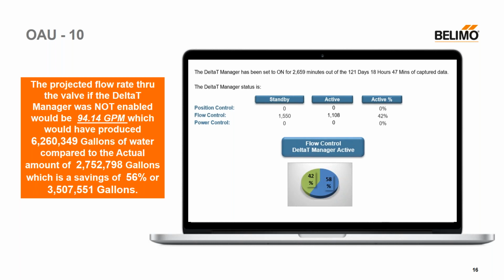The system was trying to push too much water through. I would have inefficiently used that water, essentially just passed it through the coil, not taken a heat exchange or heat transfer out of that water, and been very inefficient. For this particular valve, that accounted for roughly 3.5 million gallons of water over that time period that would have just been wasted.